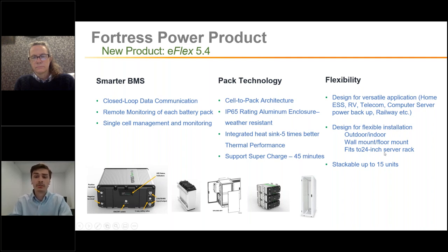It can also fit into a 24-inch standard server rack, where you could put 3 or 4 in a rack and then parallel racks together. The eFlex is stackable up to 15 units for 80 kilowatt hours. The eVault, a larger battery, is stackable up to 12 for 200 kilowatt hours, which is why we call that the smaller commercial space option. The eFlex is the flexible unit, stackable up to 80 kilowatt hours, but has closed-loop communication and indoor-outdoor capability.